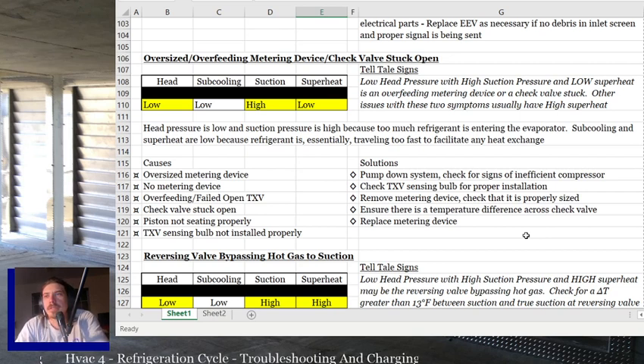Solutions are pump down the system, check for signs of an inefficient compressor, because that's the other issue it could be. But it's probably not, because that's usually high superheat. Check TXV sensing bulb for proper installation. Remove a metering device. Check that it's properly sized. Ensure that there's a temperature difference across the check valve. If there's check valves in it, make sure that it's not stuck open. If you're reading the same temperatures on both sides of that check valve, it's stuck open. If it's supposed to be closed and it's not, then the check valve's bad.